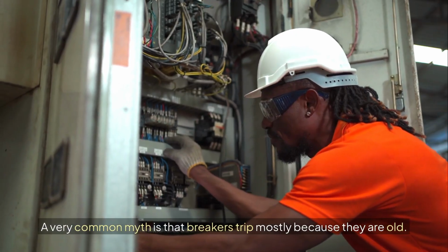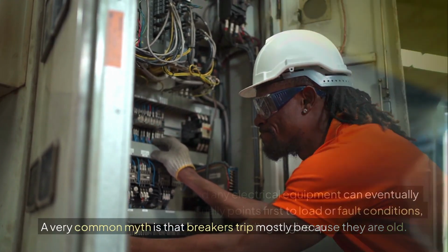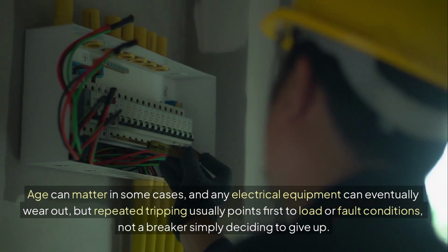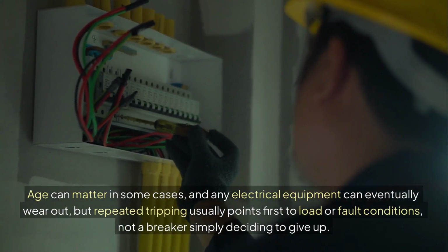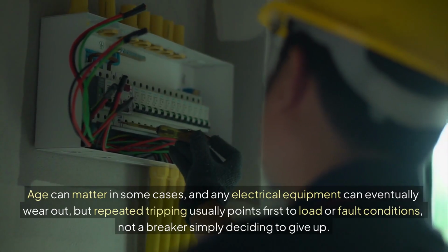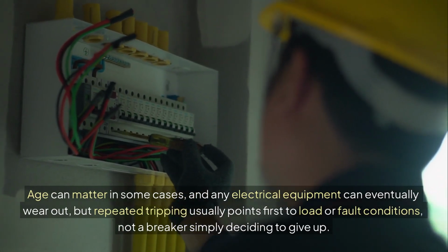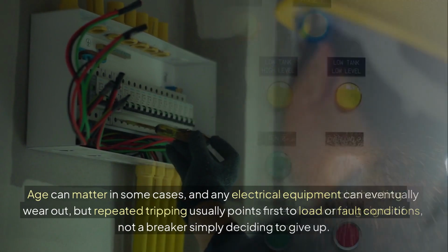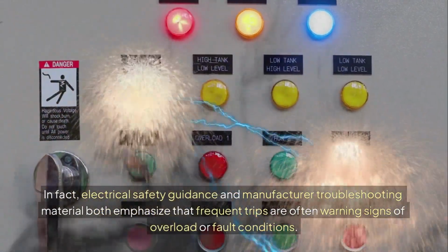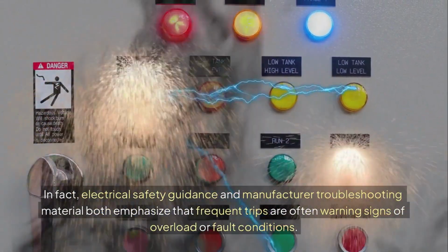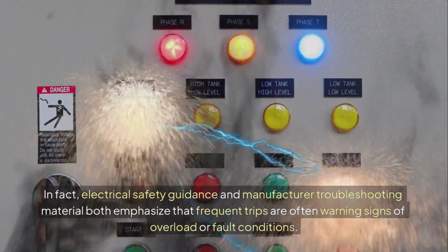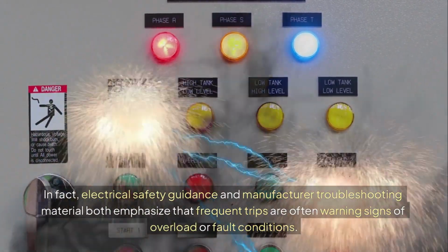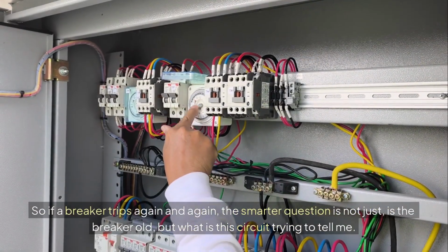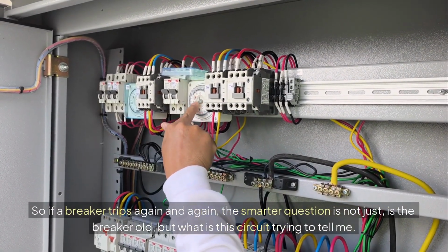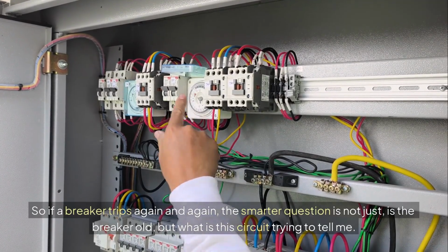Myth versus reality. A very common myth is that breakers trip mostly because they are old. Age can matter in some cases, and any electrical equipment can eventually wear out, but repeated tripping usually points first to load or fault conditions, not a breaker simply deciding to give up. In fact, electrical safety guidance and manufacturer troubleshooting material both emphasize that frequent trips are often warning signs of overload or fault conditions. So if a breaker trips again and again, the smarter question is not just, is the breaker old, but what is this circuit trying to tell me?